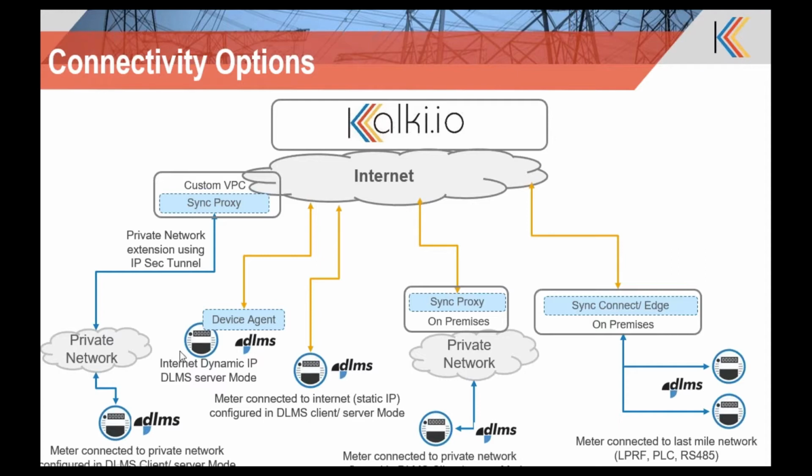So another option is having meters with a dynamic IP SIM card, and these meters need to connect with Kalki.io. One option we have is the device agent, a small software stack which we provide that can be implemented on the modem or the meter, and this will take care of connecting with Kalki.io and creating the tunnel. And once the tunnel is created, the DLMS communication happens through the tunnel.